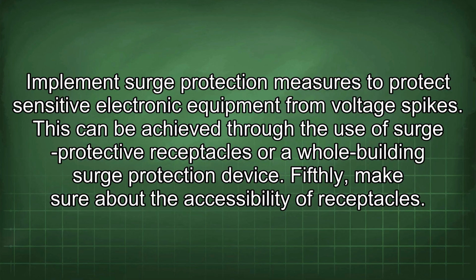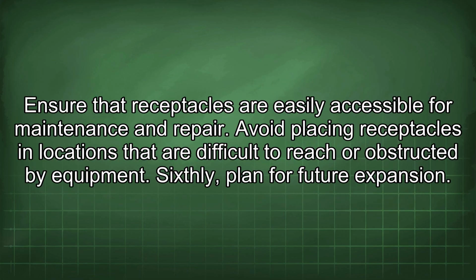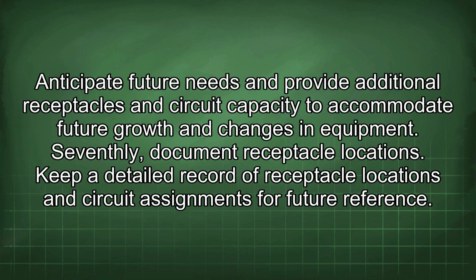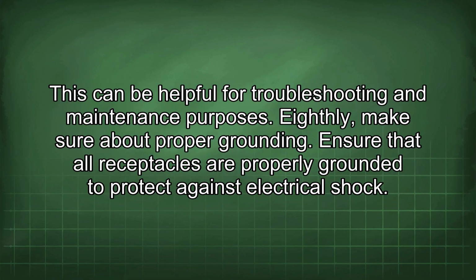Fifthly, make sure about the accessibility of receptacles. Ensure that receptacles are easily accessible for maintenance and repair. Avoid placing receptacles in locations that are difficult to reach or obstructed by equipment. Sixthly, plan for future expansion. Anticipate future needs and provide additional receptacles and circuit capacity to accommodate future growth and changes in equipment. Seventhly, document receptacle locations. Keep a detailed record of receptacle locations and circuit assignments for future reference. This can be helpful for troubleshooting and maintenance purposes.